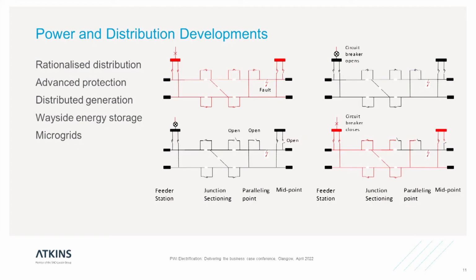Rationalised distribution. Alan was talking about footprints. We can look at the sequence of diagrams on the right, showing how we can potentially move to a position where a single circuit breaker controls the whole of a feeding section. If you get a fault, you open the circuit breaker, isolating the whole section, then remotely open the switches around the fault, reclose the circuit breaker, and carry on operation. All that can happen within milliseconds.